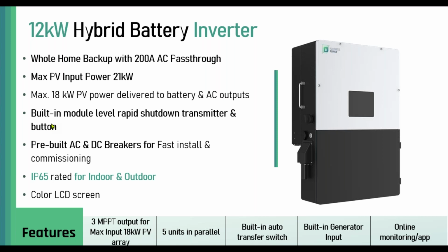Okay, and then I'll talk more about the power ratings as we progress. You can put 5 units in parallel, although we are working to expand our paralleling capabilities, maybe up to 10 units in parallel as well. It has a built-in generator input up to 90 amps. You can hook up your generator input up to 90 amps, and the generator input will also serve as the AC coupling method. So you can put either a generator in the generator input or the AC coupling input, up to 90 amps.